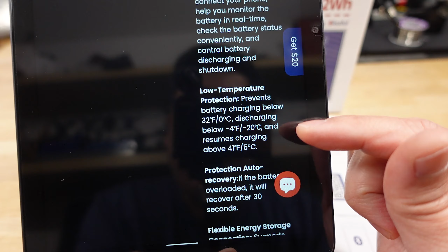If it's in a discharge state and the temperature falls below -4 degrees Fahrenheit, it will prevent the battery from further discharging. When it's extremely cold, those protections come in because lithium iron phosphate does not like the cold. If you try to charge the battery below 32 degrees Fahrenheit, it will pretty much destroy it. That's why those protections are in place.